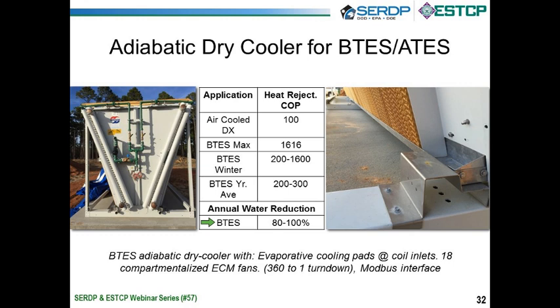So, a nice piece of technology with 18 fans, two dry coolers, and 15% minimum speed on the ECMs. We can have a 360 to 1 turndown, which is incredible. So we can slow these things around. They're typically lopping along slow at night. We never run the fans any faster than 50%. And just to give you a comparison about something no one ever talks about, COP of heat rejection. What does that even mean? How many kilowatt hours do I have to spend to dump a kilowatt hour into the air?